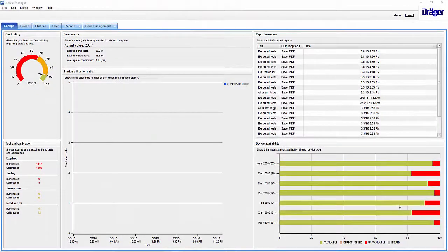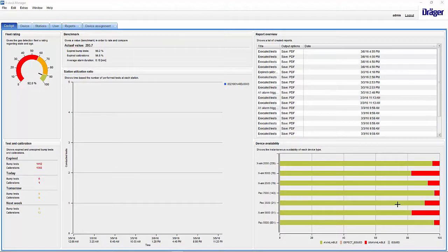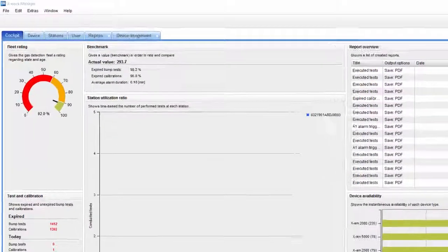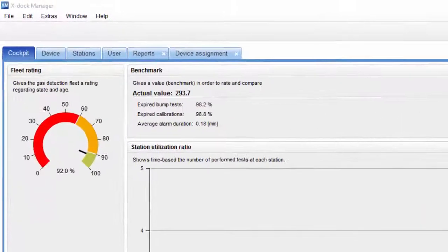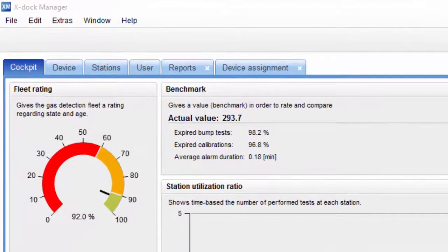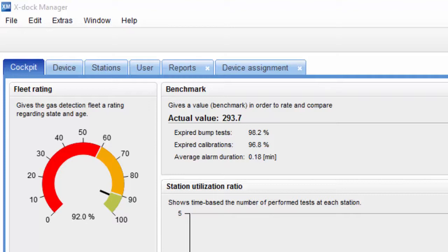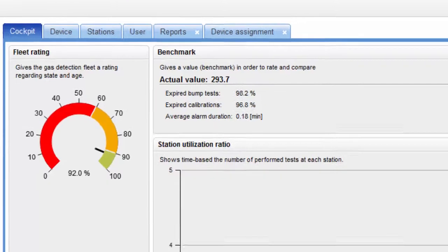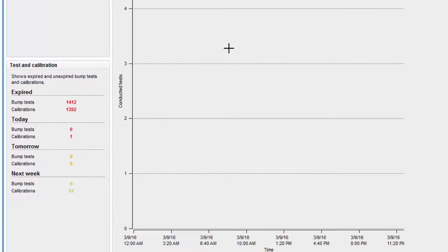Once all intervals have been defined in the instruments, you need to maintain the intervals for the fleet. The X-dock Manager is an ideal tool for this. The cockpit provides a clear overview of the registered instruments. The Test and Calibration section gives us an overview of how many instruments are overdue or will need to be tested and calibrated within the next few days.